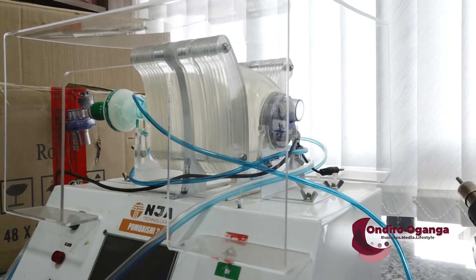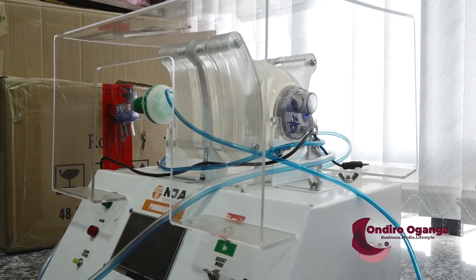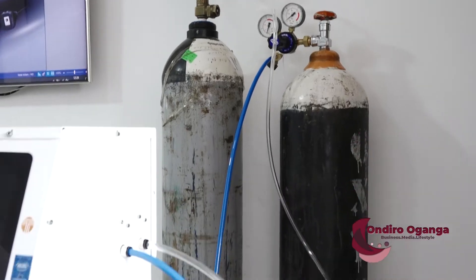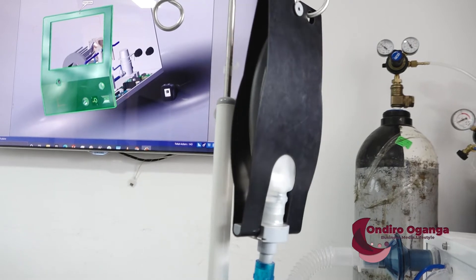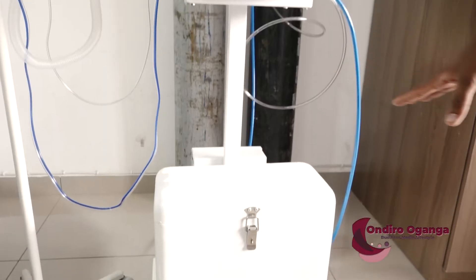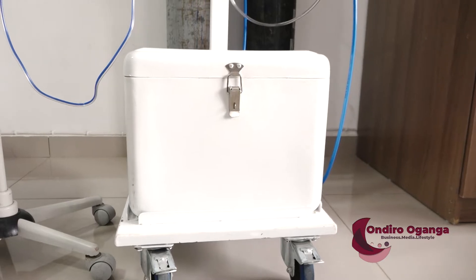So they ended up changing the design and going for an electronic control system. That is how Pumuaishi 3.0 — an intensive care unit ventilator which can be used on pediatric and adult patients weighing up to 180 kg — was born. The ventilator has since received approval from the Kenya Bureau of Standards. It uses battery power with a solar battery, enabling use in remote places as long as you have a couple of solar panels.